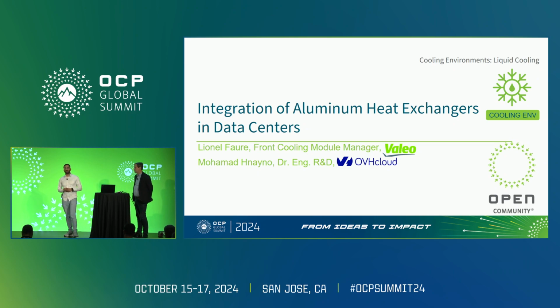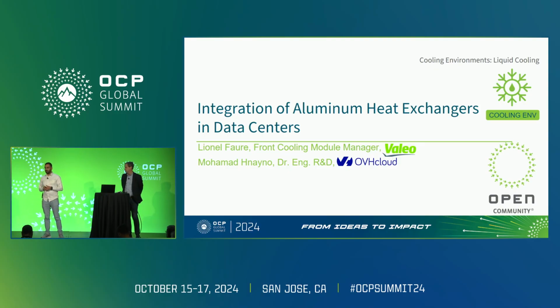One important thing about Ovhcloud, we have deployed our water cooling system since day one. So since 2003, we have our liquid cooling solution, our own cooling solution within our data center. And we have a combination of two types of technology. The first one is the direct-to-chip liquid cooling in order to cool the processor, the CPUs and GPUs, and air cooling solution to cool the other equipment like the motherboard, hard disk, and RAMs.